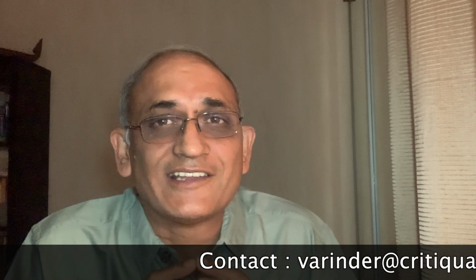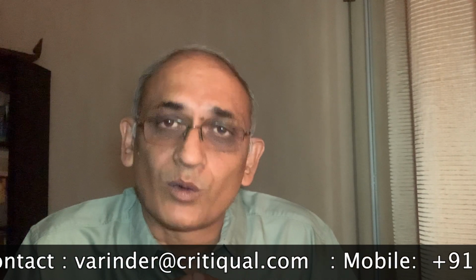Follow your company policy if there is one. If not, then follow the OEM's advice. In the worst case scenario, have your instruments calibrated once every 2 years. And also make sure that you collect a calibration certificate from the calibrating agency. The certificate should clearly indicate the details of the reference meter or the standards used, and also the time validity of the calibration. Normally, the calibrating agencies would give a validity of 1 year only.